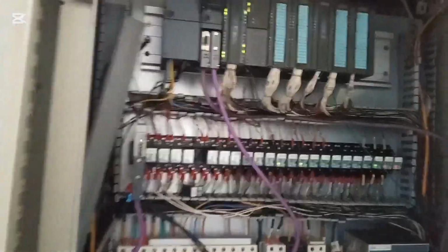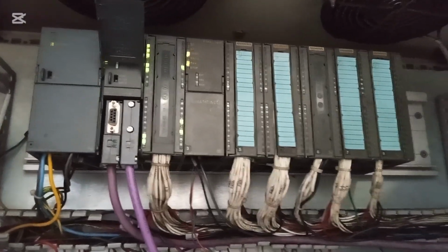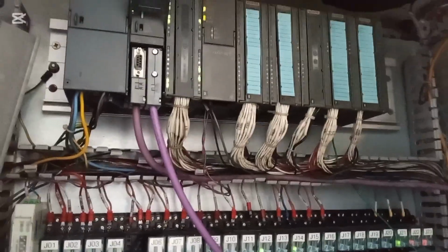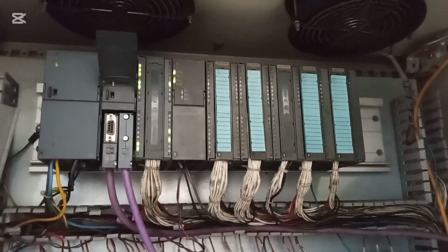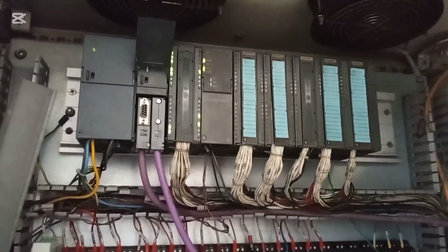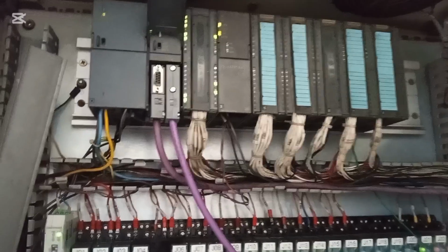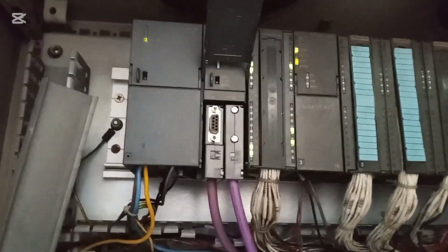To overcome this hang state, at first we checked our PLC, but there was no alarm, although the blower was running. To find out the problem, when the plant was in shutdown condition, we stopped the power supply.